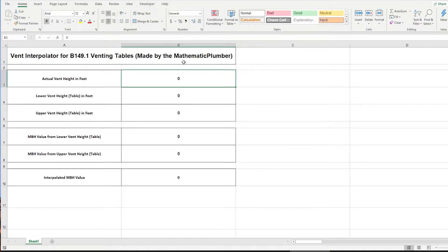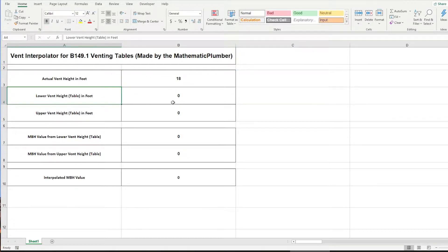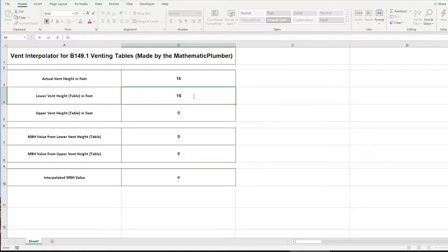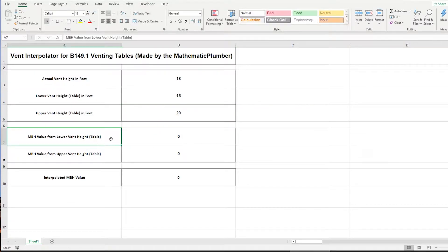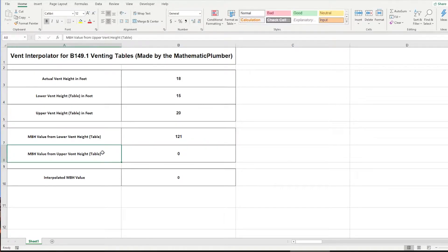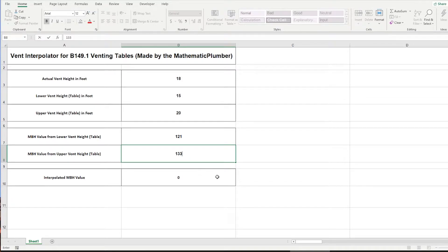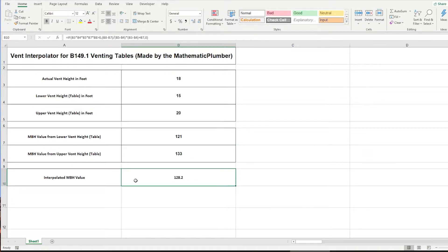First, enter the actual vent height in feet — click that box and type in 18. Lower vent height table is 15 feet, upper vent height is 20 feet. Enter the MBH value from the lower vent height table: 121 MBH. Then enter the MBH value from the upper vent height table: 133. And look at that — it spits out an interpolated MBH value of 128.2, just like we calculated before.